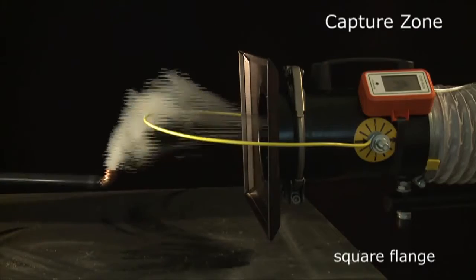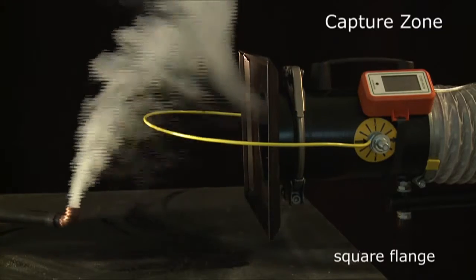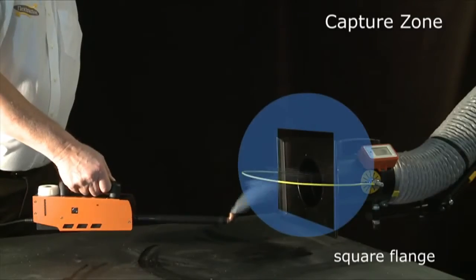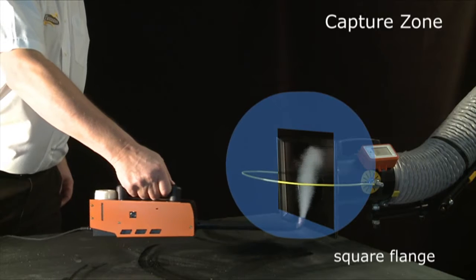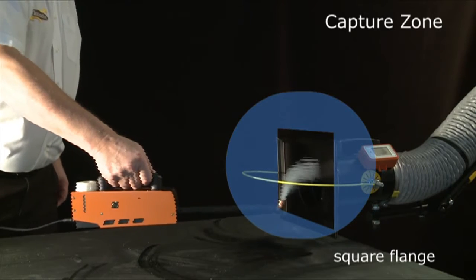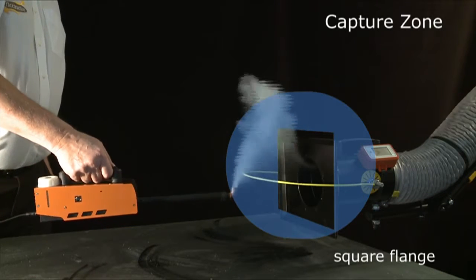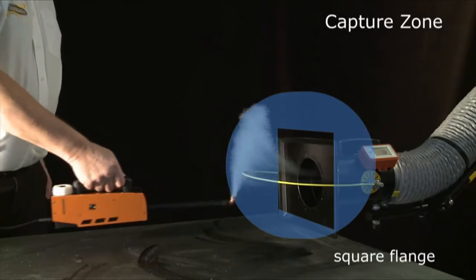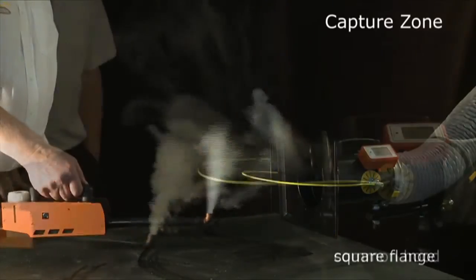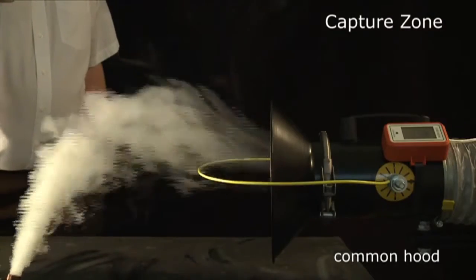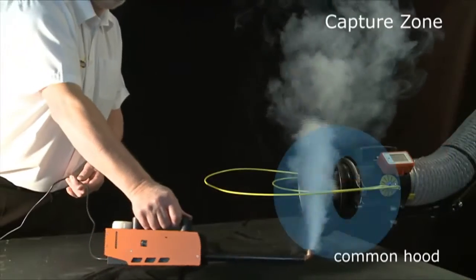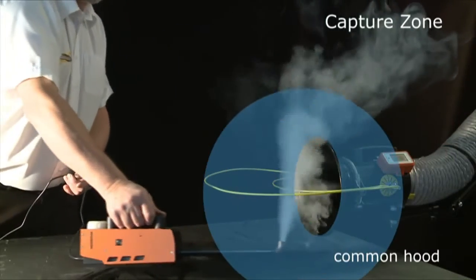A flange restricts the movement of air from behind a hood, changing the shape and extending the capture zone in front of the hood. It reduces turbulence in the airflow into the hood, which improves the effectiveness. The shape of the flange is also a factor. A flared inlet is even more effective.